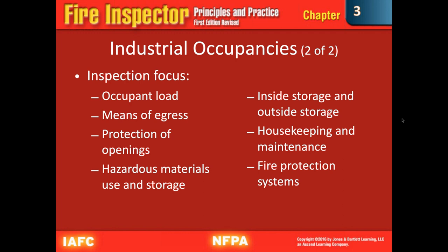So if a fire alarm goes off, how are you going to know if all you hear is the deafening roar of the equipment that's around you? So when you walk into these places as an inspector, think about that. Be like, all right, look, you have fire alarms. They're going to go off, but is anybody going to hear it? So you may want to make sure that they have good visual cues as well when you're doing your inspections.